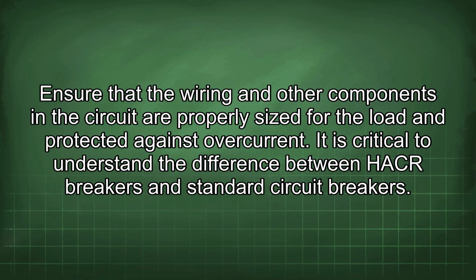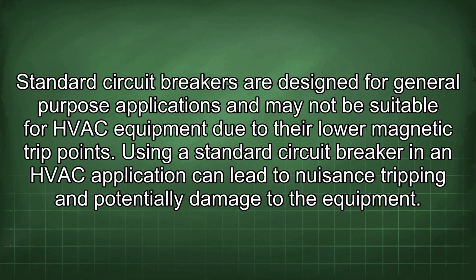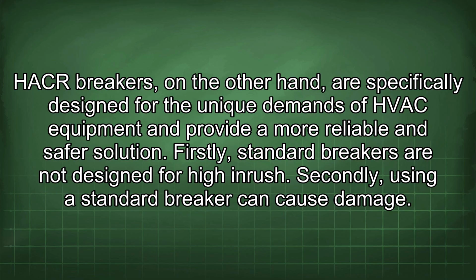It is critical to understand the difference between HACR breakers and standard circuit breakers. Standard circuit breakers are designed for general-purpose applications and may not be suitable for HVAC equipment due to their low magnetic trip points. Using a standard circuit breaker in an HVAC application can lead to nuisance tripping and potentially damage to the equipment. HACR breakers, on the other hand, are specifically designed for the unique demands of HVAC equipment and provide a more reliable and safer solution. Firstly, standard breakers are not designed for high inrush. Secondly, using a standard breaker can cause damage.